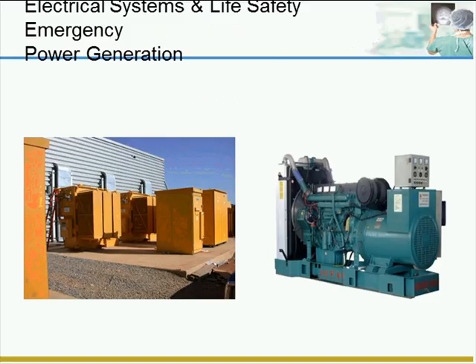Getting into some electrical system equipment, the picture to the left shows a set of step-up transformers. This looks like a series of transformers feeding a local utility, probably a small production facility of some kind. The picture on the right shows a package type emergency generator, probably a 300 or 400 kilowatt unit. This will be a common size found at a medical facility. You may have one, two, three, or even four or five of these units connected. These could be internal to the building, or they could be package units located outside of the building.